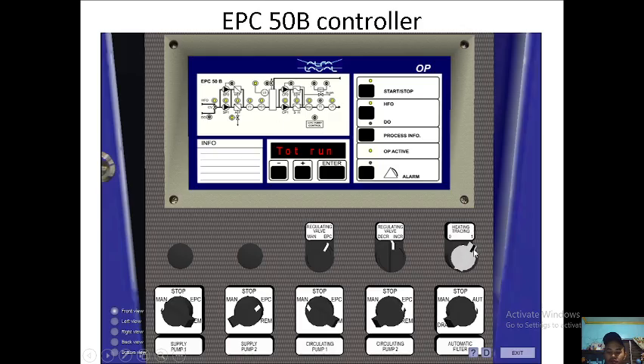The heat tracing, so this one will be on so that if the system is stopped, the cabinet will have a heater to prevent condensation in the electrical parts and to heat up the components. Here we have manual control, automatic control, stop, and remote control for our supply pumps and circulating pumps. And we have automatic for the automatic filter, and stop for the filter. We have manual. You can use the manual filter, or we can drain or backwash the filter, or drain if you want maintenance.